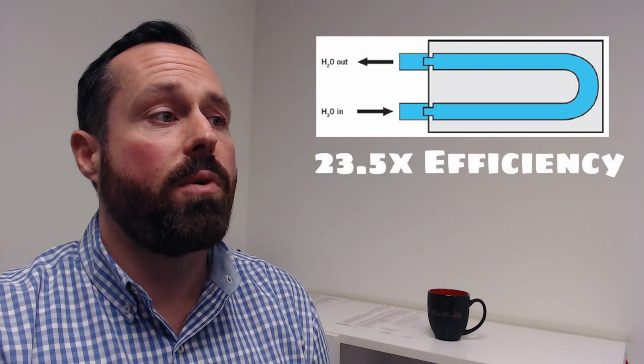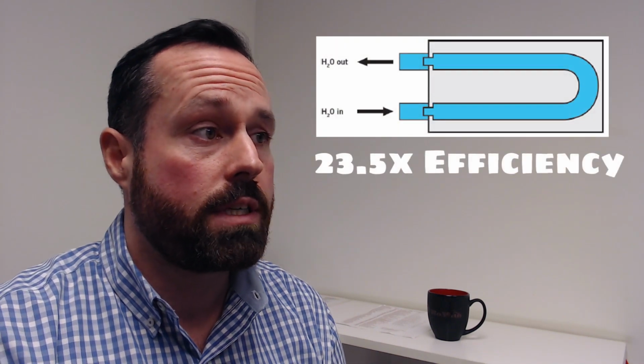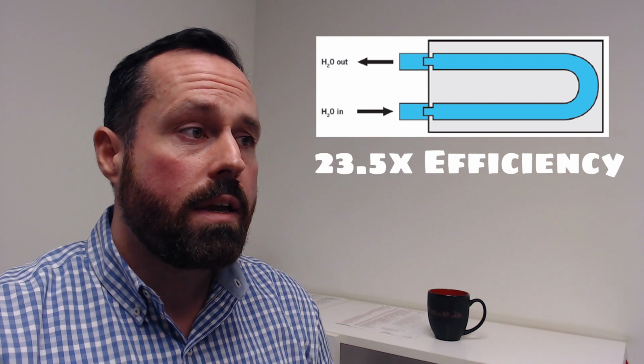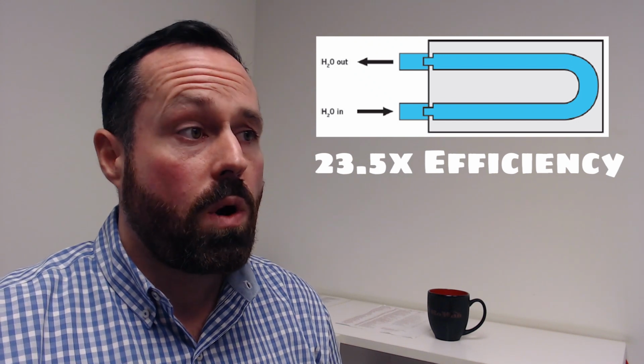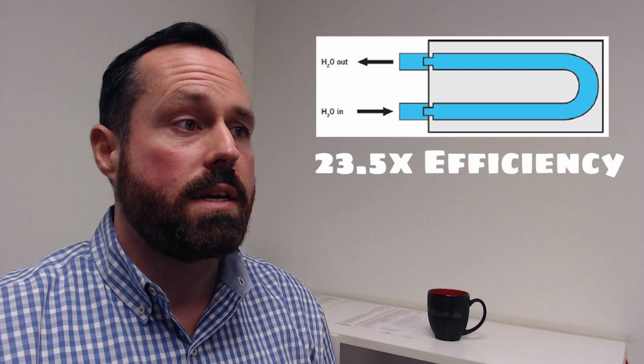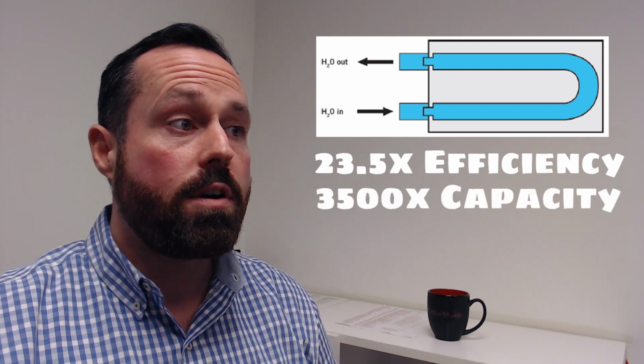Water is 23.5 times more efficient at transferring heat than air. Further, given a specific volume of water flow over a component, water has a heat carrying capacity of nearly 3,500 times that of air. That's an incredible improvement in efficiency over air-cooled transformers.